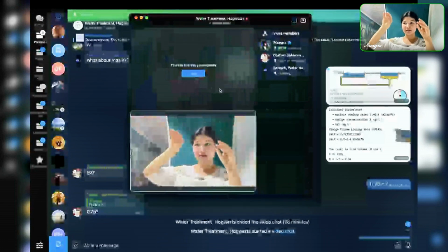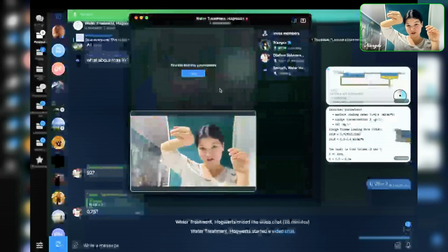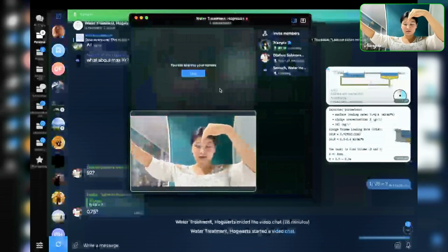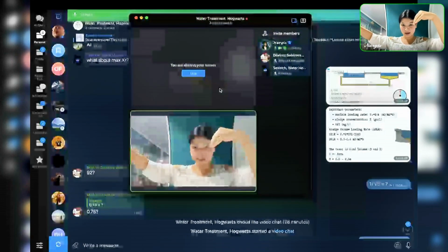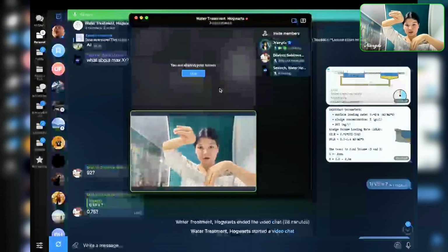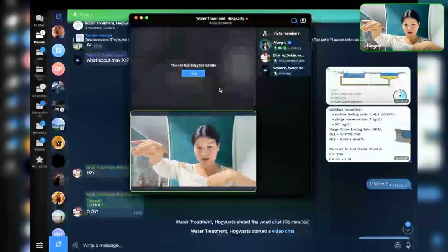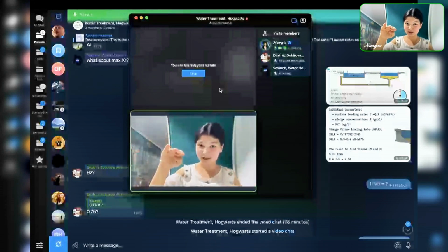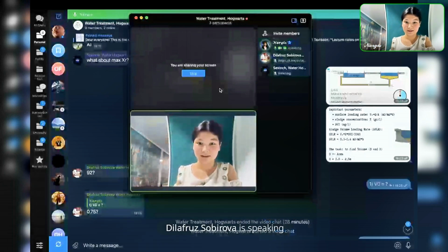So first you should draw the box around the secondary clarifier. You see that 5,000 meters cubed is leaving from one side. And from the downside, half of whatever is coming to the wastewater treatment plant is leaving, which is 2,500, right? From this side, 5,000 is leaving. From this side, 2,500 is leaving. So what is coming in? 7,500, in fact, right?